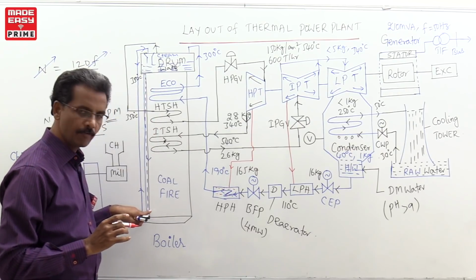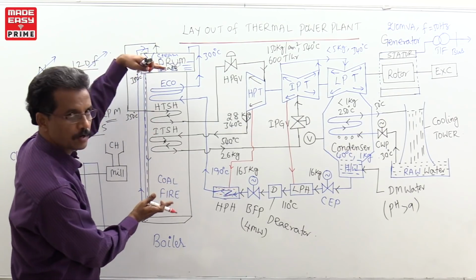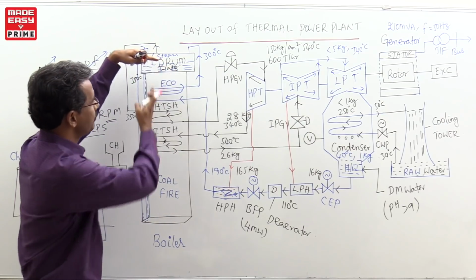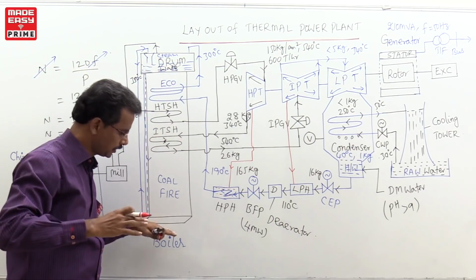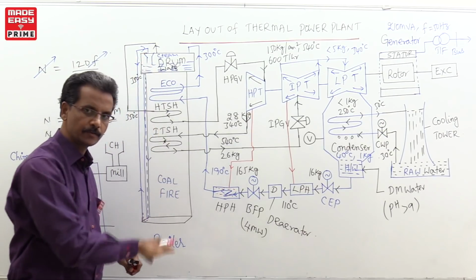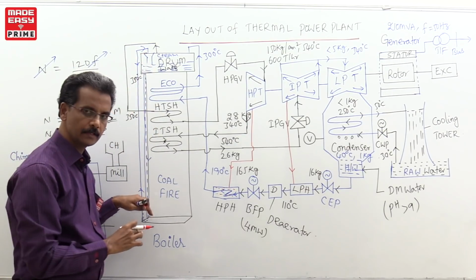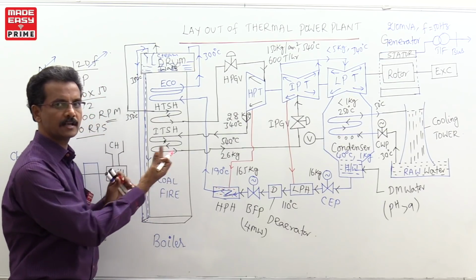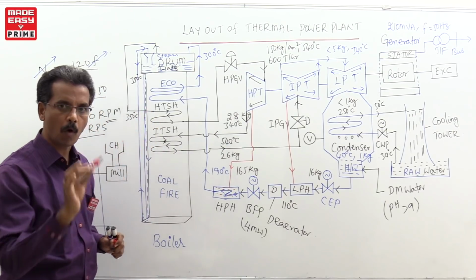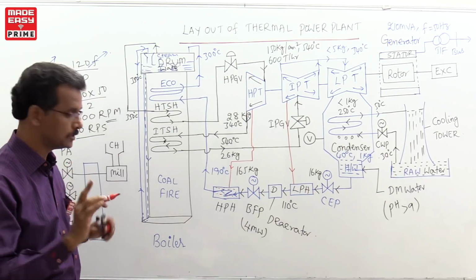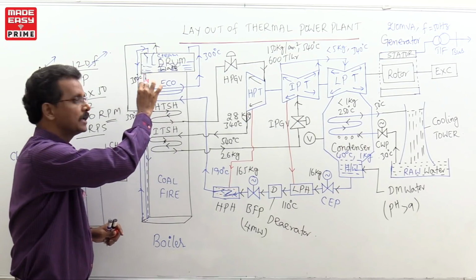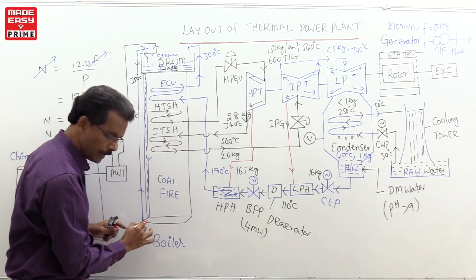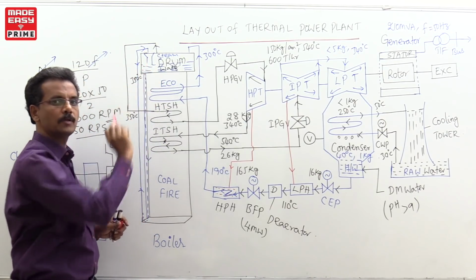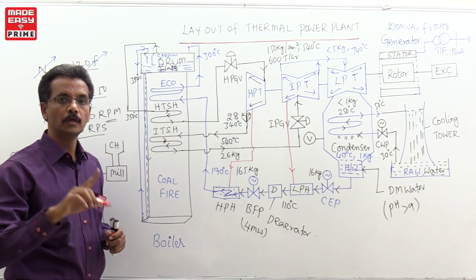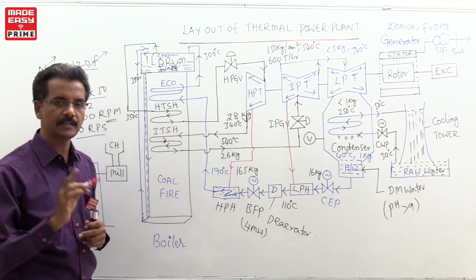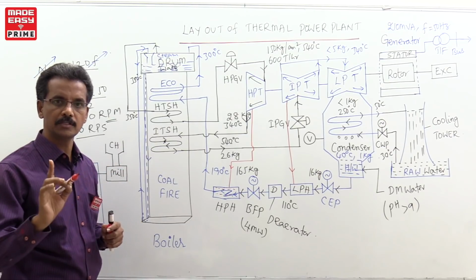So water is falling from the boiler drum, normally at a height of around 100 meters. From the height of 100 meters of the boiler drum to the ground level, water will fall naturally through gravity. By the time it rises and comes back, it will gain heat, and the water is converting to steam. So the density difference of water and steam is used for circulation of the water from the drum to the boiler and once again back to the drum. It is mainly due to the density difference of water and steam. That type of circulation is called natural circulation.